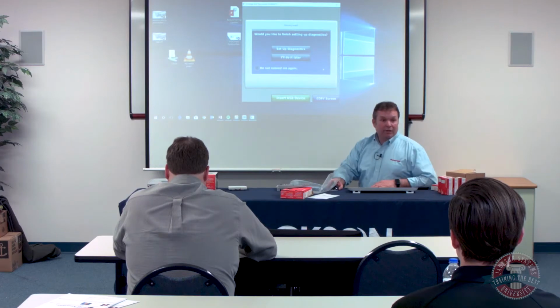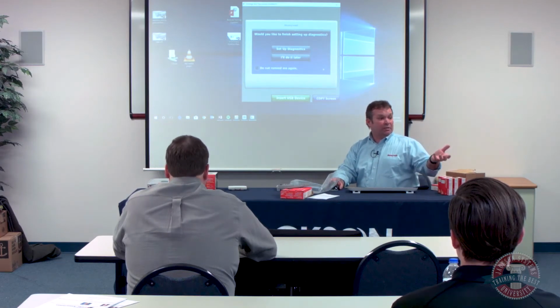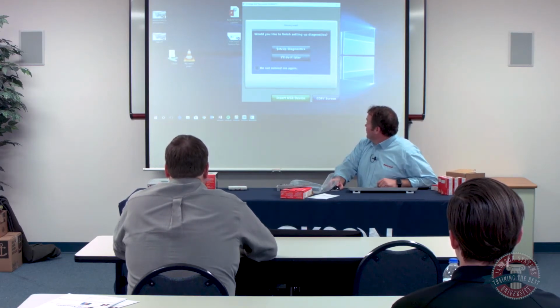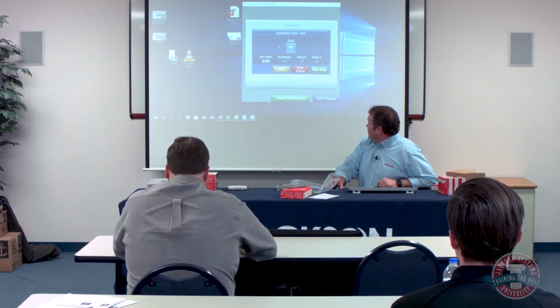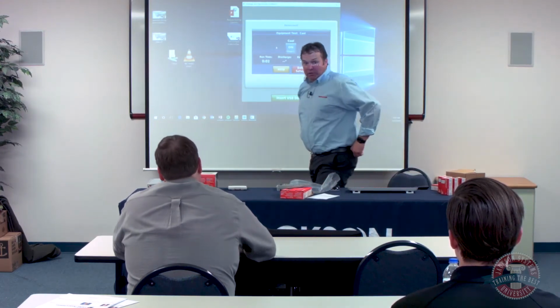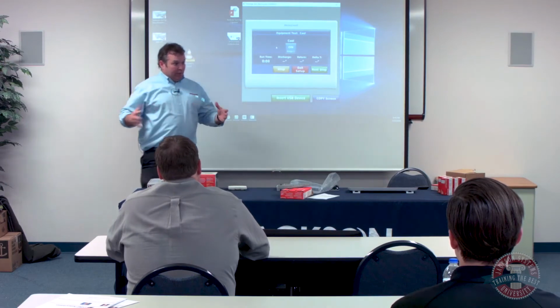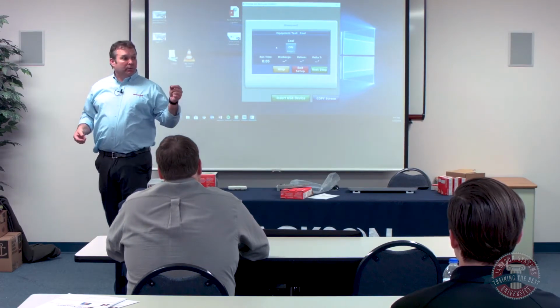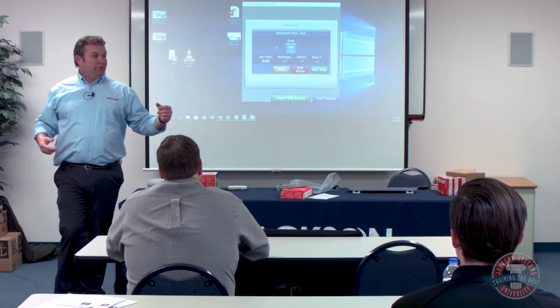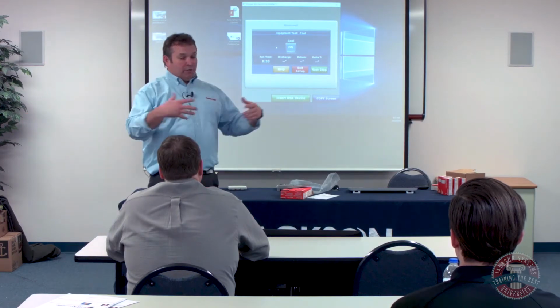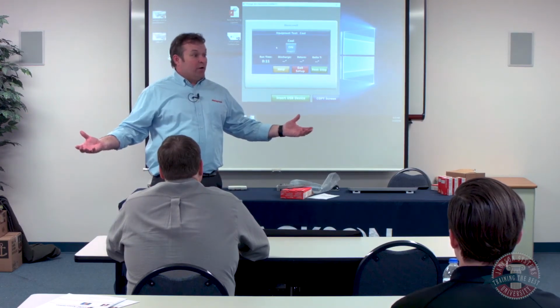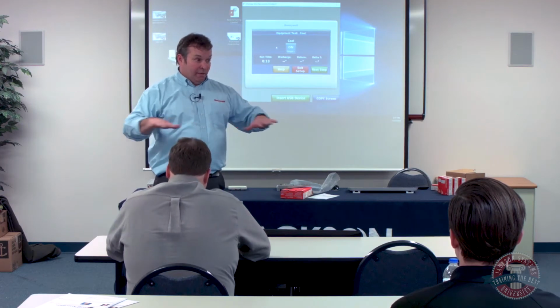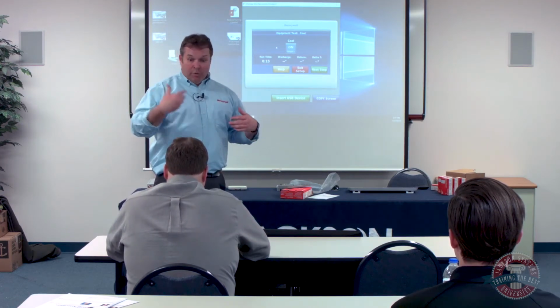Then it's going to prompt you to set up your diagnostics, and I'm going to let it do it. The first thing I'll do is turn on cool stage 1 and let that run. Now if this is a new install, when you first introduce your Freon and turn that stuff on, you've got to let it run for like 15 minutes to equalize before you start doing all that.